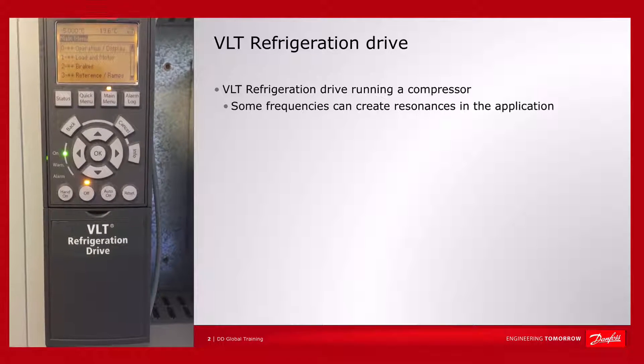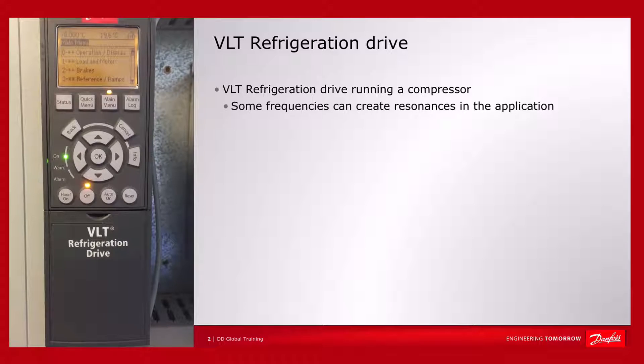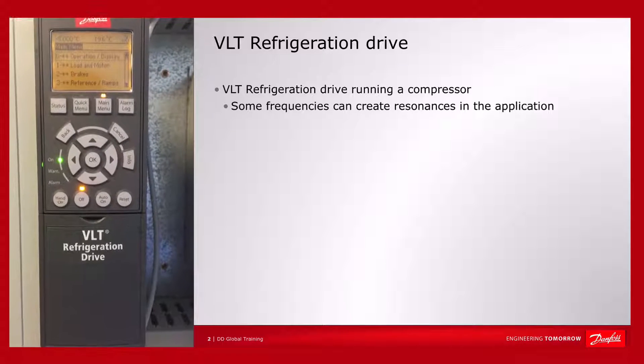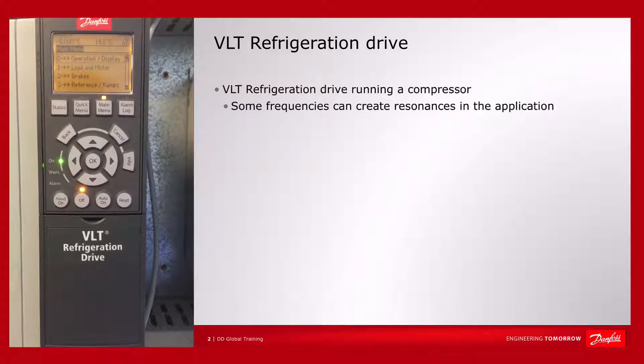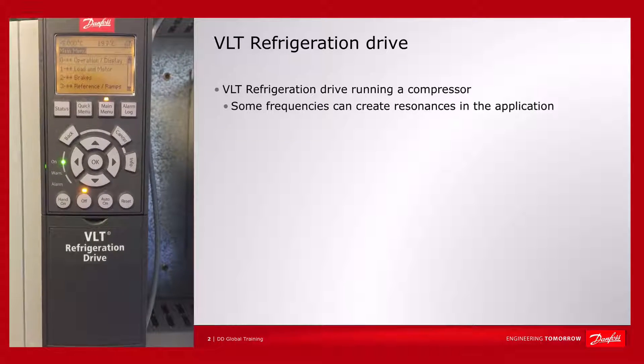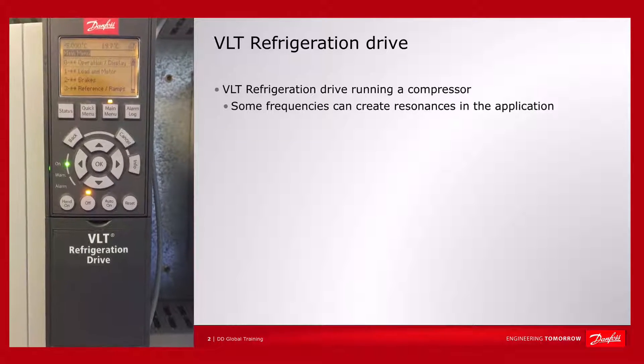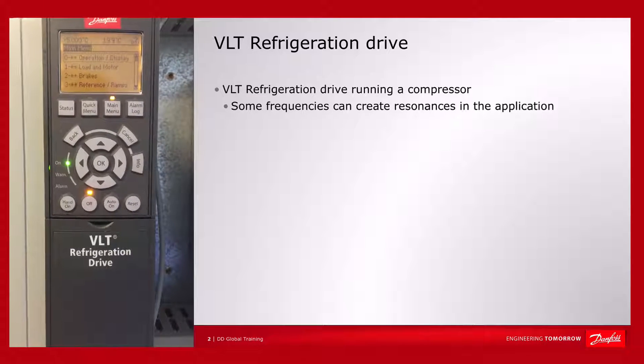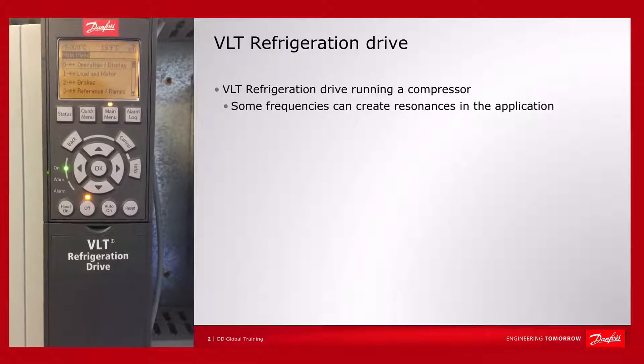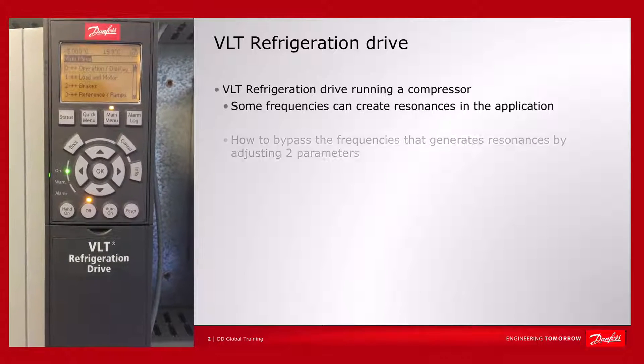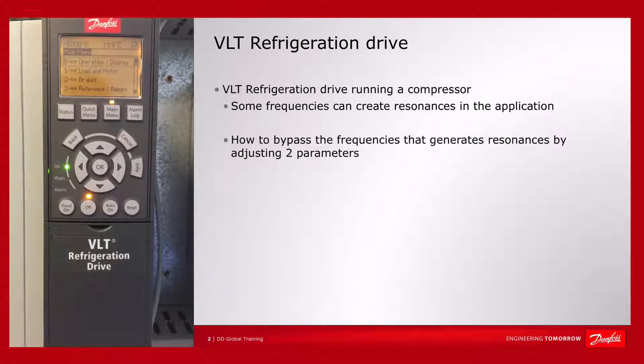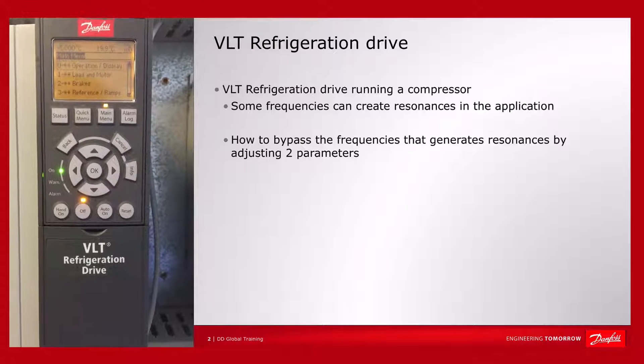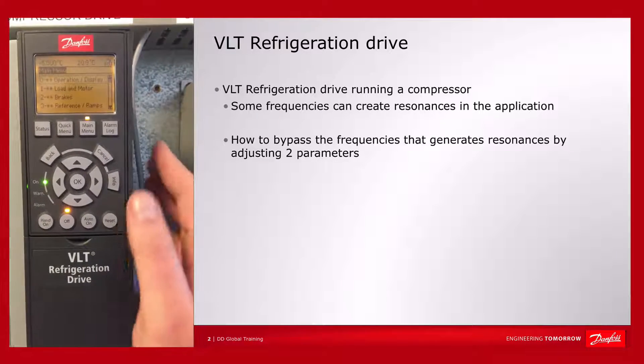We have a refrigeration drive running a compressor, and we have found out that some of the frequencies create resonances in the application. I'll show you how you can bypass some of the frequencies that create resonances by just adjusting two parameters.